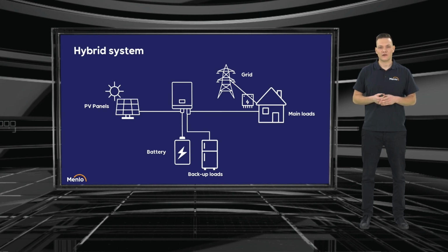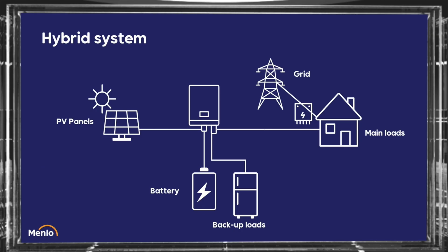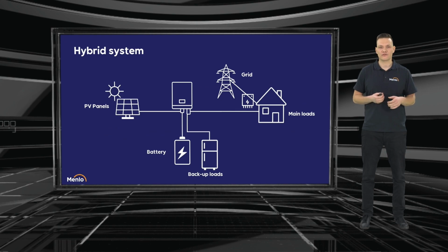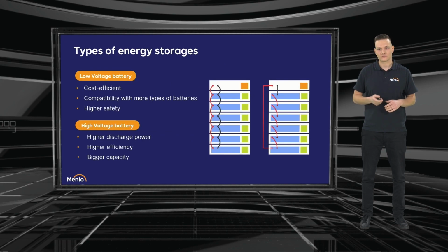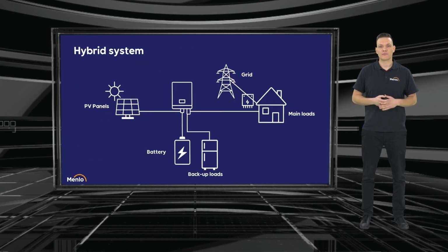So here we can see how the hybrid system looks. We have the grid, the main loads, and then we connect it to the inverter. We have the PV panels, battery, and backup loads. So when a power outage happens, the inverter disconnects from the grid and the main loads and supplies backup loads with energy from the battery and from the PV panels. An important feature here is the energy meter, which calculates the consumption and the production, so the energy flow to the grid or from the grid. Based on that energy flow, it charges or discharges the battery.